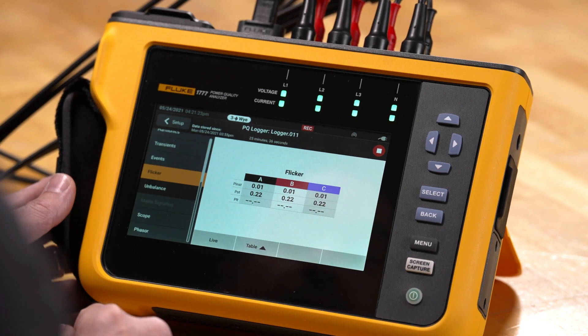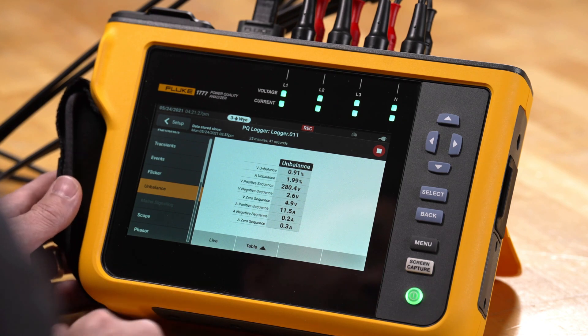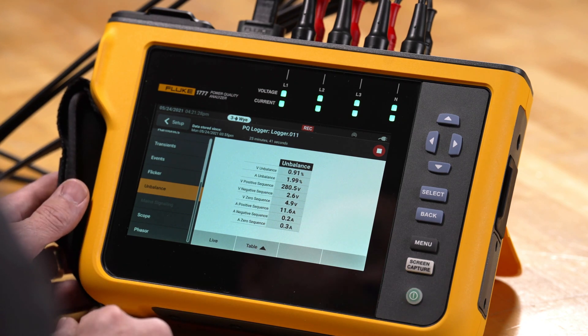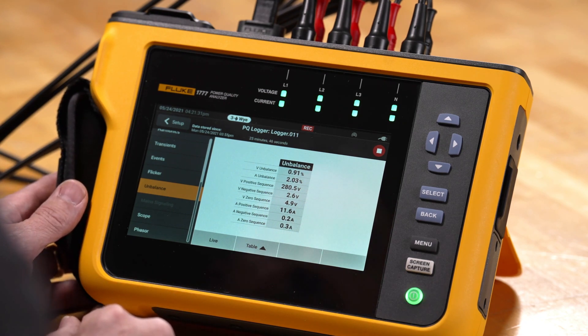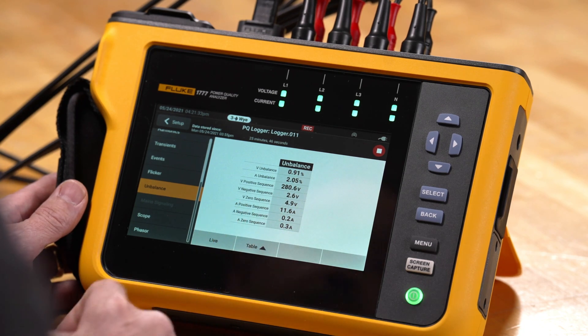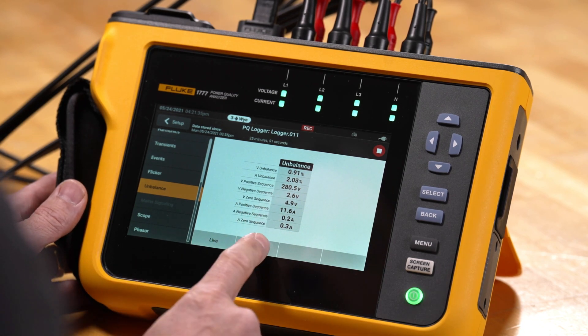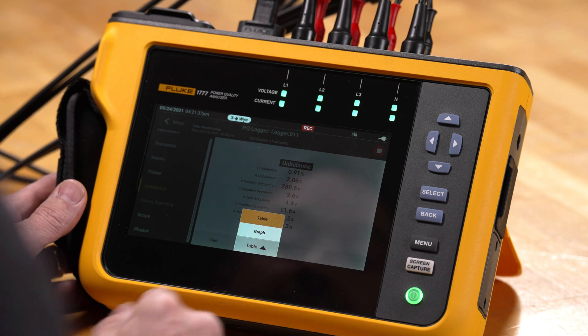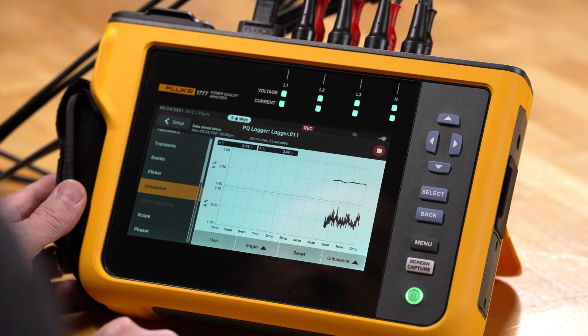We can look at unbalance data. For example, if you're doing motor testing, we can see what kind of unbalance we're looking at for voltage and current unbalance, and we can see those numbers live. We can also go to a graph view to see that information.